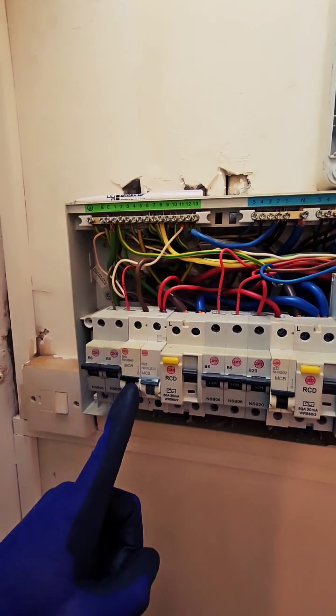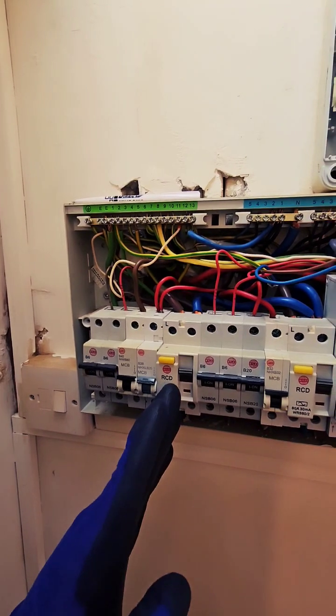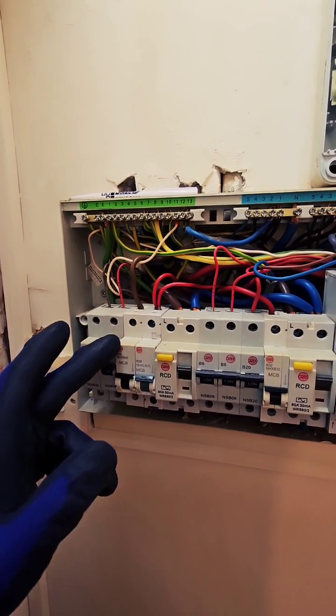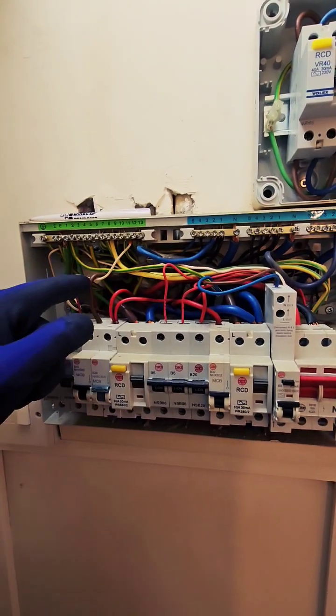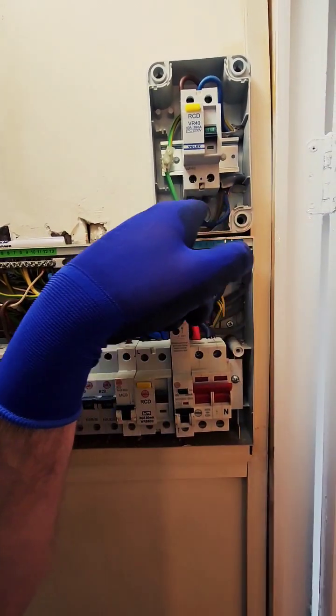This circuit here, the B40 MCB, it's on this RCD — RCD2 or whatever you want to call it. B40, 40 amp, we've got a 6mm cable. I think that's for the shower. If you follow that round, it's the new one — the brown and blue goes through here into the trunking and into here.